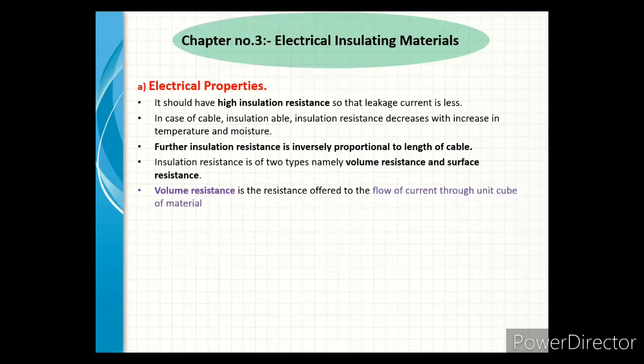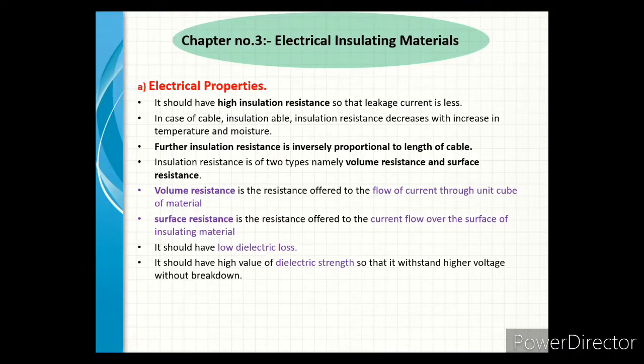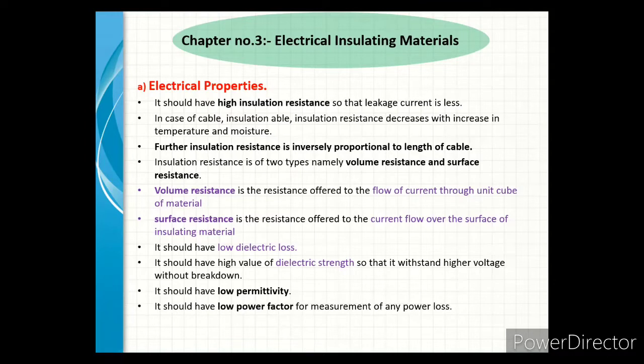Volume resistance is the resistance offered to flow of current through a unit cube of material. Surface resistance is the resistance offered to the current flow over the surface of insulating material. It should have low dielectric losses. It should have a high value of dielectric strength so that it can withstand higher voltage without breakdown. It should have low permittivity and low power factor for measurement of any power loss.